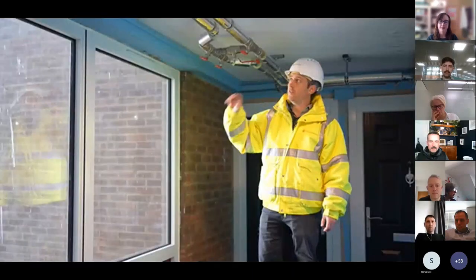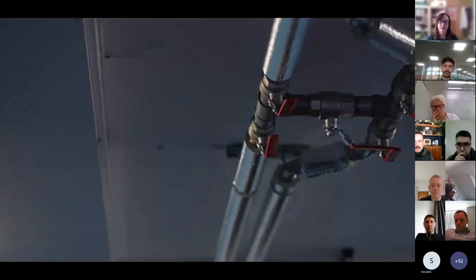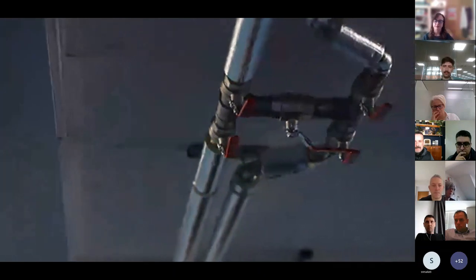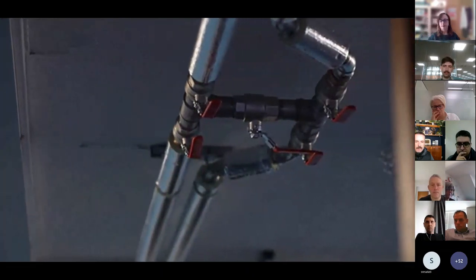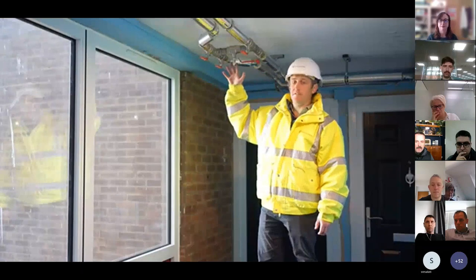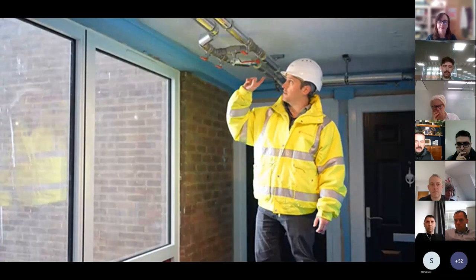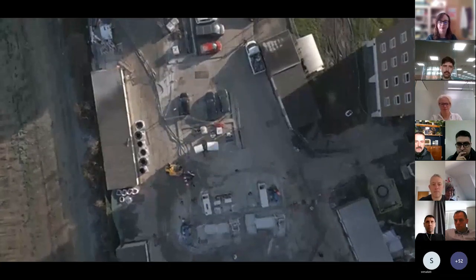Once we've teed off into each individual apartment, we come into the five-way valve arrangement here. What this allows us to do through this set of valves is close the two valves into the apartment and actually circulate flow from here all the way down through the ground array.